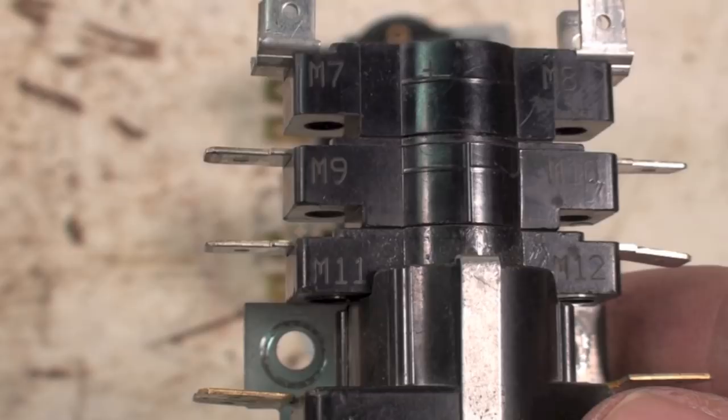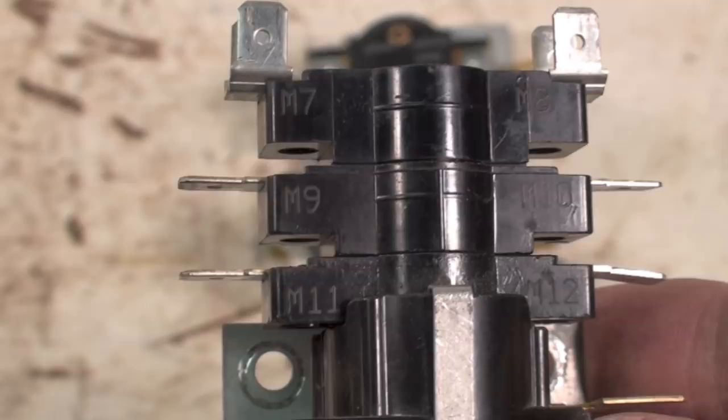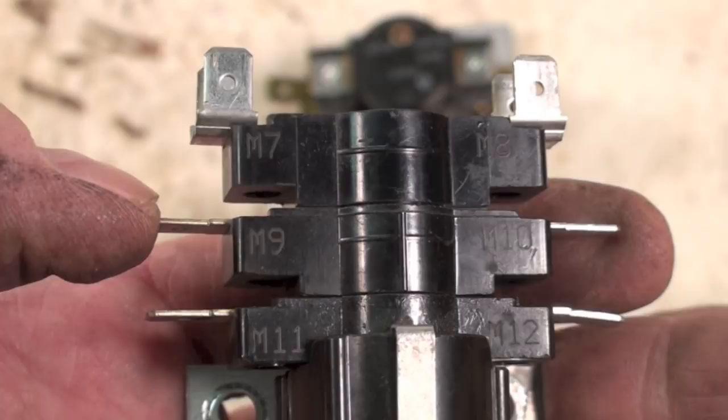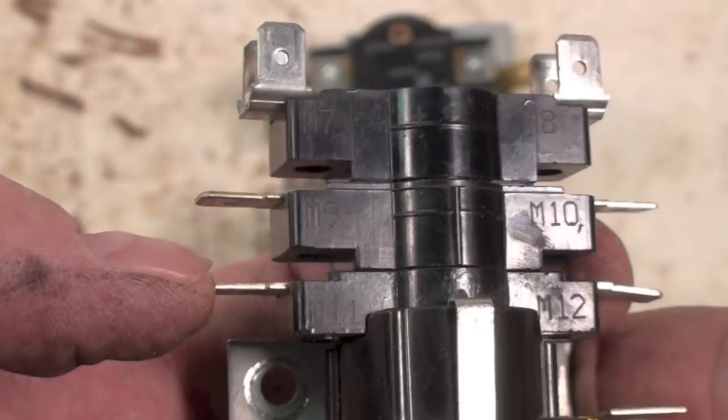This sequencer here, specifically, this one would be timed later because the higher the number on the M, the longer it takes for it to go on and the sooner it takes to shut off. Let me explain it a little better. This M9 and M10 are not going to come on when M7 and M8 come on. They're going to come on at a later time, and then 11 and 12 are going to come on later yet.